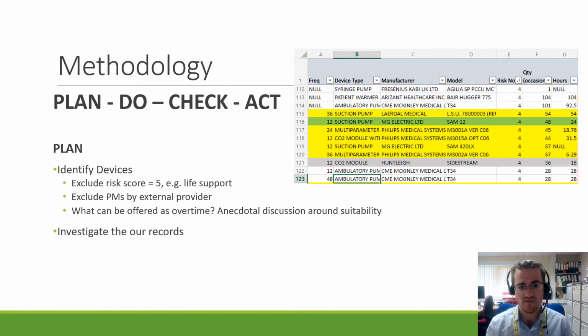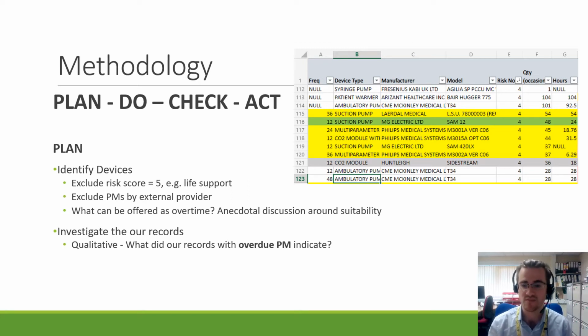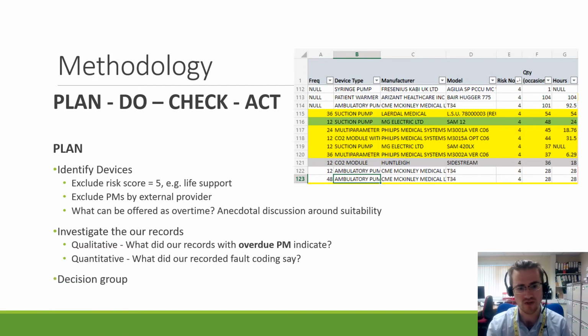Then we needed to investigate our records, which took a bit more time and effort. So we used qualitative analysis to look at any overdue PMs, again easily extracting that data from all those work orders from our asset management database. And then we'd also extract the quantitative data. So we apply shorthand, very simplified fault coding to monitor key performance indicators. So things like electrical faults, mechanical faults, just easier to group them together. And then we bring this evidence to a decision group where we would have a back and forth to see what was an appropriate risk to take forward.